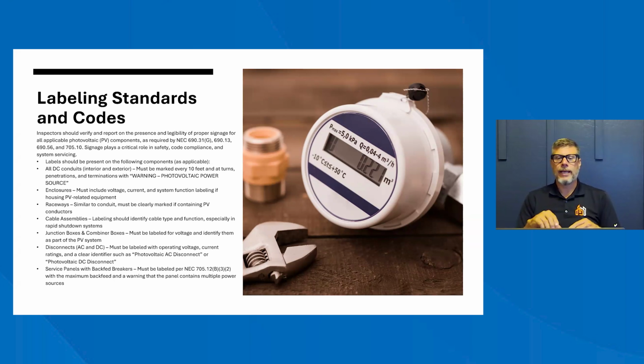All of your DC disconnects must be labeled with their function. They need to be permanent, weather resistant, and clearly visible. For your raceways, cable trays, enclosures, and all of your conduit, they need to have a warning that says "Warning: Photovoltaic Power Source." They need to be labeled every 10 feet minimum.